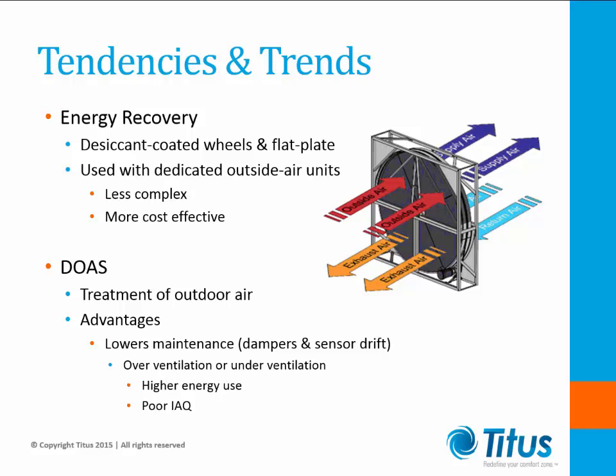A better approach for many buildings is consolidating all the outdoor air treatment into a dedicated air handling unit that will supply 100% outdoor air. Treated air from these units can be supplied directly to occupied spaces and can be injected into mixing boxes in other air handling units dedicated for temperature control. While the addition of a dedicated outdoor air handling unit might first sound like a far more expensive approach, their use may add little to the overall cost of the job, and they can allow simplification of the air handling unit.